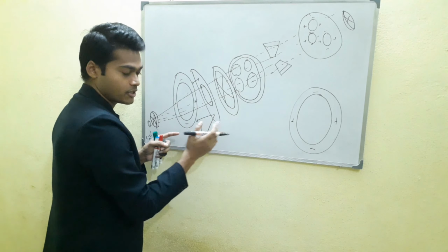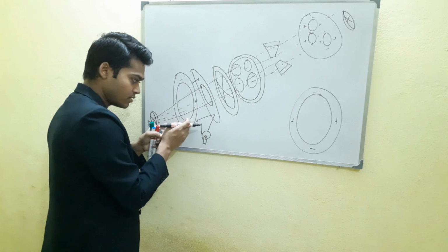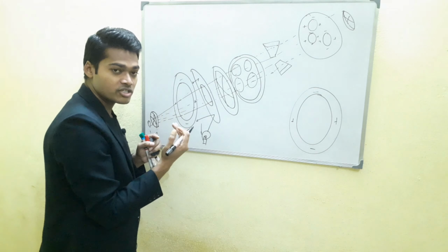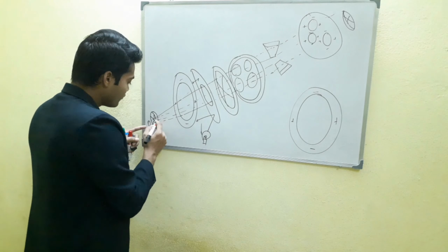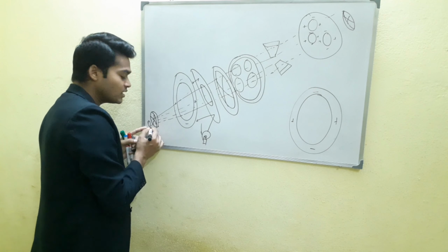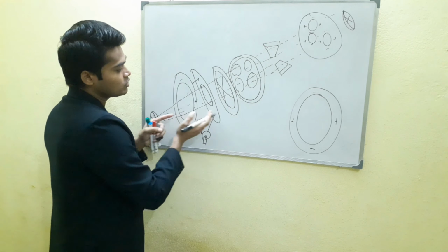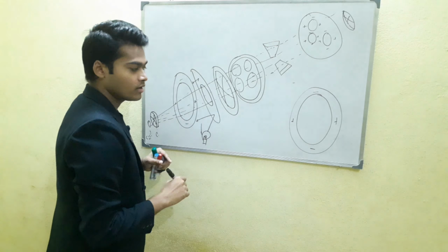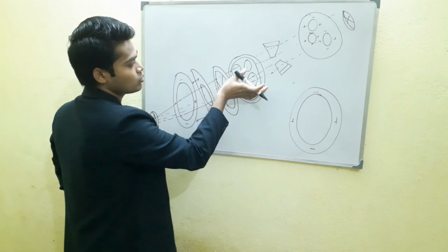just assume this is the object. After reflecting the light, it falls here and forms the image on the cornea, because the cornea has a curvature shape and acts like a mirror, right. After acting like a curved cornea, it forms the image behind the cornea. Then this image crosses through this separate element, right. When the light crosses through this condensing lens, it crosses through the aperture.